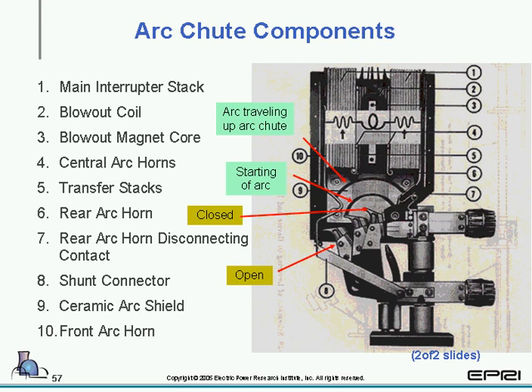Here we have a blown out example of the arc chute components, and we'll take a look at the nomenclature. It normally helps you pretty much tell what the function of each part does. Now, when the arc chute moves from the closed to the open state, as shown in the yellow, the little turquoise, you'll see that you have a starting of an arc and the arc traveling up into the arc chute. It is used to contain, cool, and direct the arc.